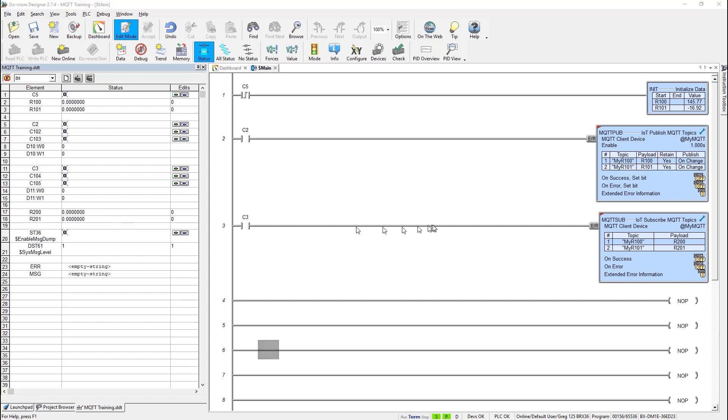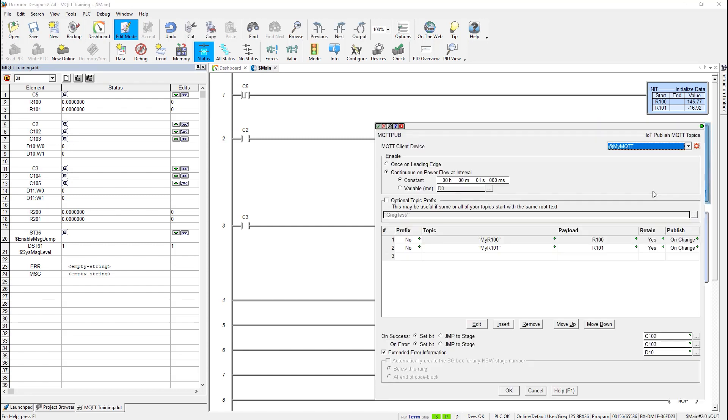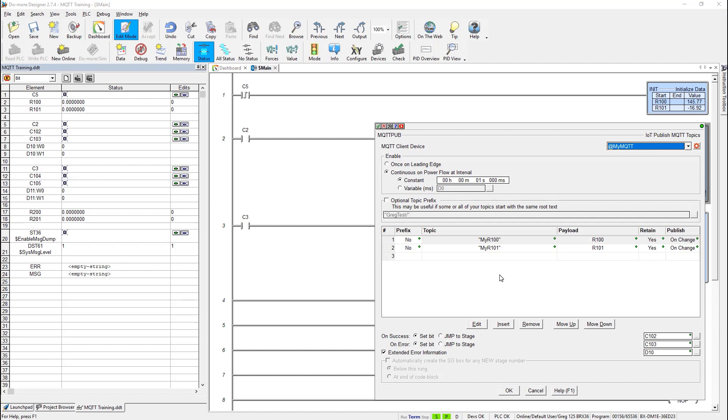So now let's look at the MQTT pub instruction. Double click on him. You notice here I picked my MQTT client device, which mine is called MyMQTT. And I have a choice here of how to enable it, whether once on a leading edge, which basically, if you have that and when you enable it, then it will just go through this list of published topics once and determine success or error. But I could also publish it continually. So here you can see I have continuous on power flow at interval. And I selected one second as the constant or the time between when I publish. And basically what that is, as long as this input is on, then it will go through this list every second and try to publish these values.